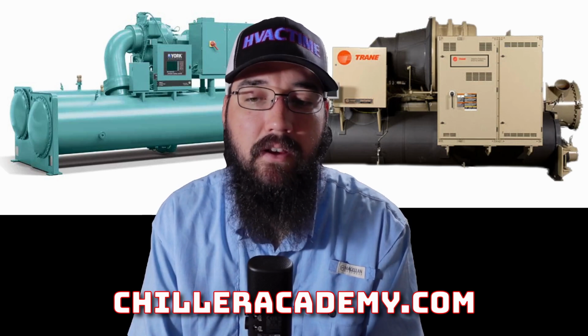And to give you some pressure examples, 134A has a 45 degree, so all of these will be 45 degree evaporators. Saturation is 40 PSI, that's gauge, all these will be gauge. 45 PSIG for 513, 410A is 130 PSIG, and R22 is 76 PSIG.